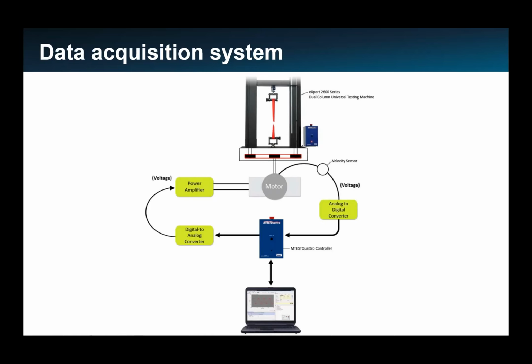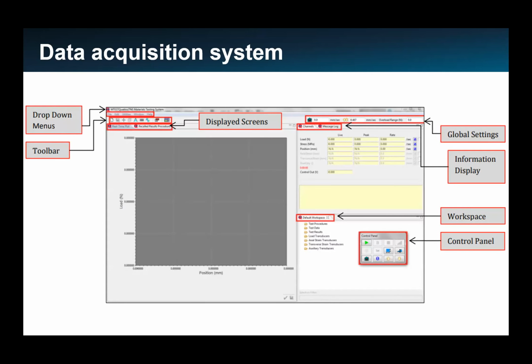Now this is how data can be acquired using a universal testing machine. First, a load cell converts the mechanical force applied to the specimen into an electrical signal. Second, a displacement sensor measures the deformation or displacement of the specimen during the test. Then the analog signals from the load cell and displacement sensor are converted into digital signals that can be processed by a computer. So the software can display the load displacement curve in real time and calculate the material properties such as stress, strain, modulus of elasticity, and ultimate tensile strength. This is how the software looks. And as mentioned before, this software collects the data and analyzes the results.